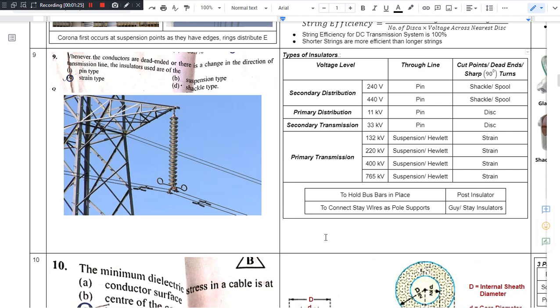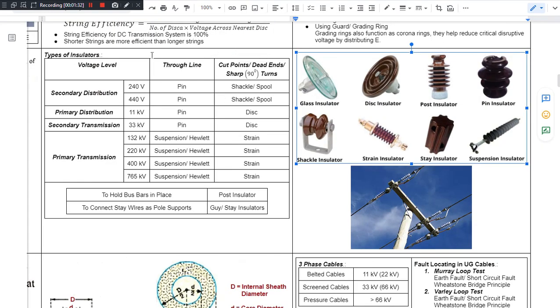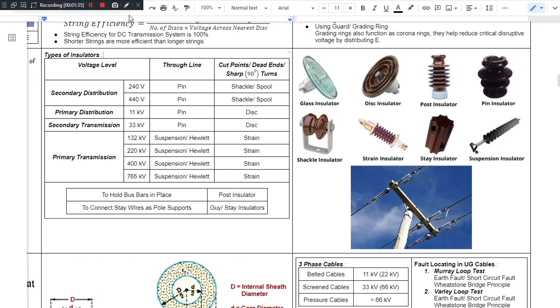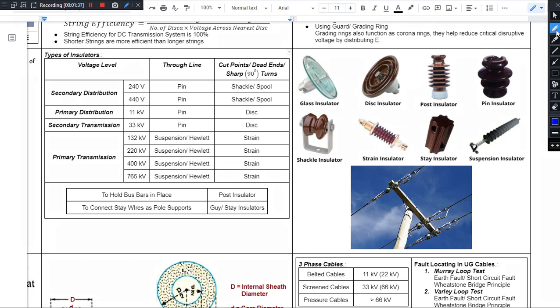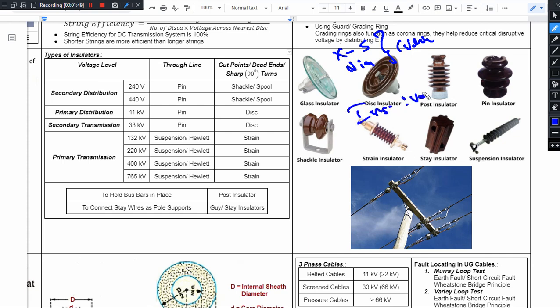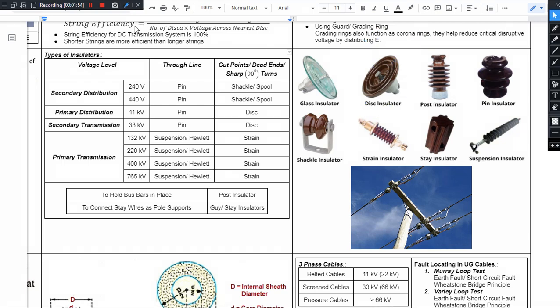In a transmission system, we choose the insulator first. The choice of insulator depends on voltage level. The cross-section or diameter of a conductor depends on current rating, while the insulation level depends on voltage. You need to remember this — cross-section area of the conductor depends on current, and insulation level depends upon voltage.